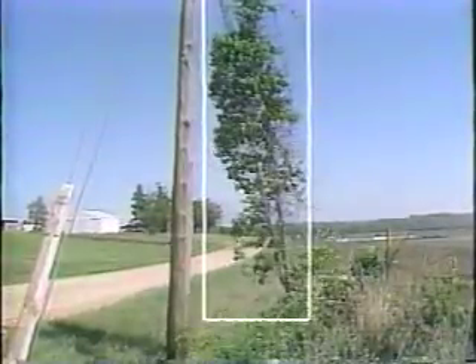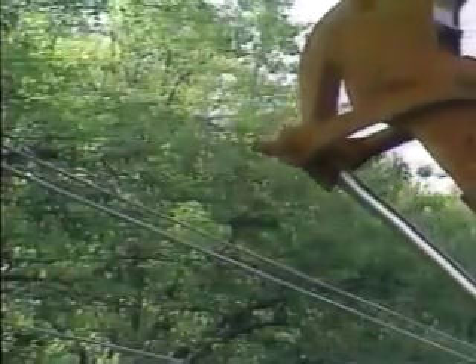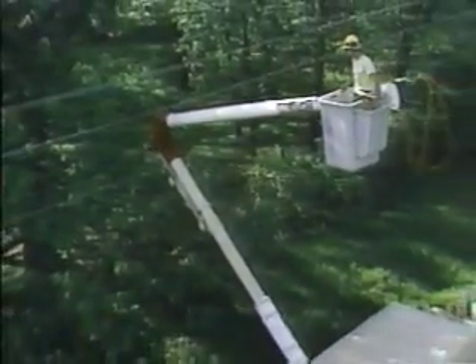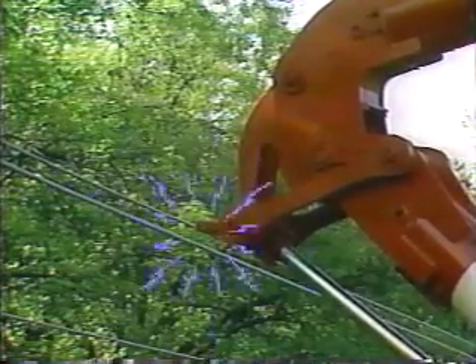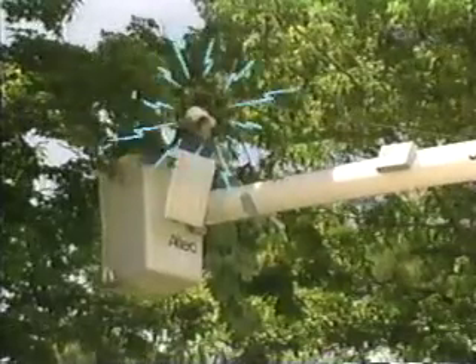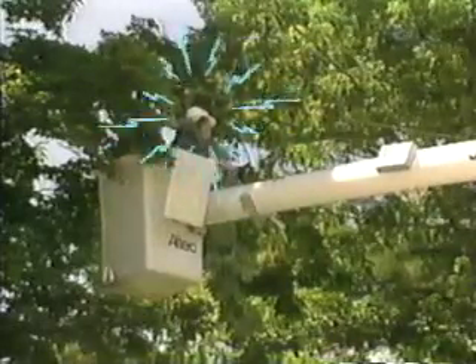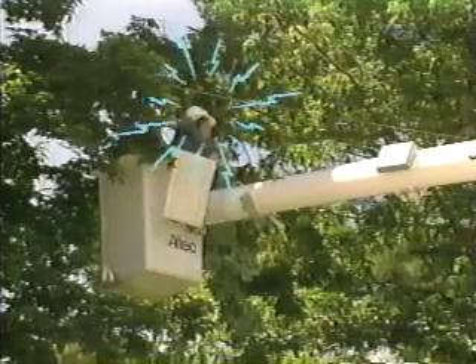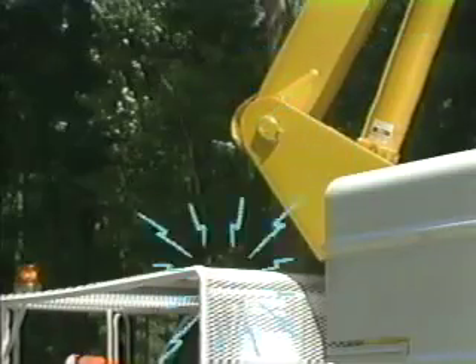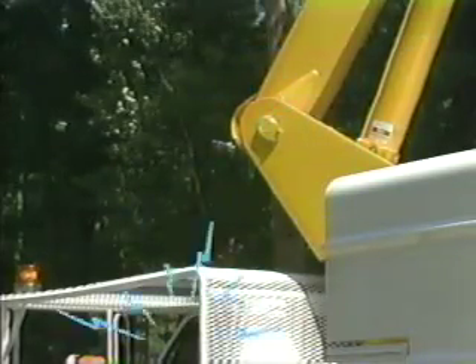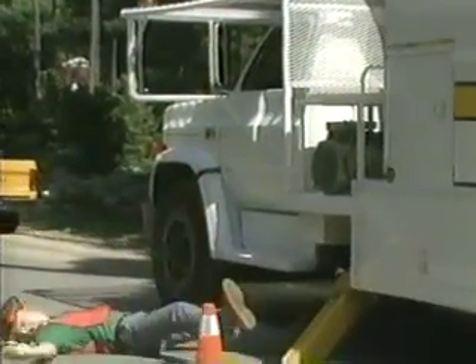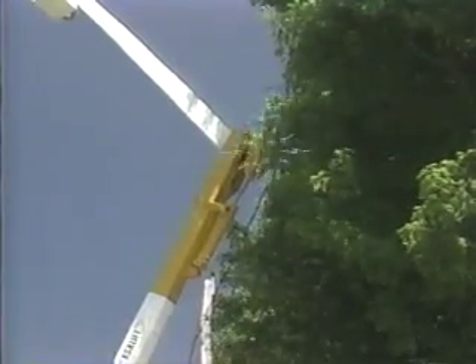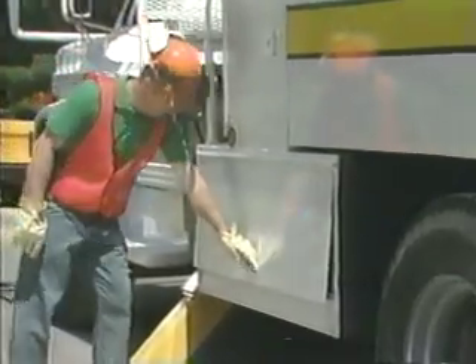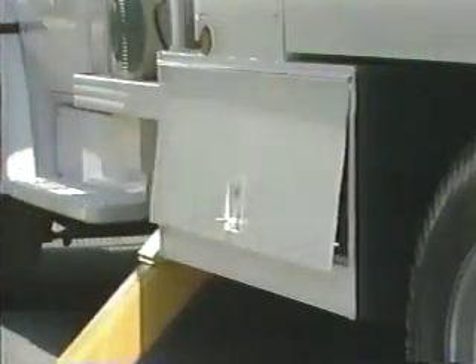Contact between a conductor and a guy wire, as a result of a vine growing into both, or even contact by an uninsulated boom, can complete a circuit. Remember, even an insulator in a boom can fail as a result of dirt contamination or delamination. If such contact occurs, the whole unit can become energized, in which case it is not only the person aloft who is vulnerable. When the circuit is completed, a ground person touching any part of this equipment and the ground at the same time would receive an electric shock by indirect contact. Ground personnel should never touch the equipment for any reason when attached booms or tools get closer than the minimum safe work distance from an energized conductor.